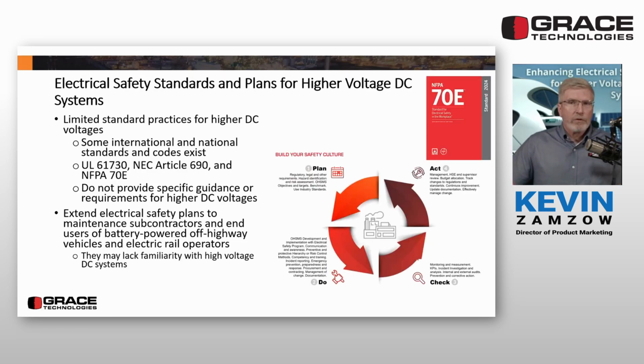Moving over to look at the standards, as solar power generation and battery electric industrial vehicles evolve, I encourage you to work with organizations to help UL, NEC, NFPA, and other standards keep up with the industry changes. Most utility, mining, and rail operation companies have an electrical safety program aligned with NFPA 70E, and many have an electrical maintenance program following NFPA 70B, which has transitioned from a recommended practice to a standard in the 2023 edition. 70E describes how to achieve an electrically safe work condition, and 70B describes the condition of maintenance of electrical equipment and systems for safety and reliability.